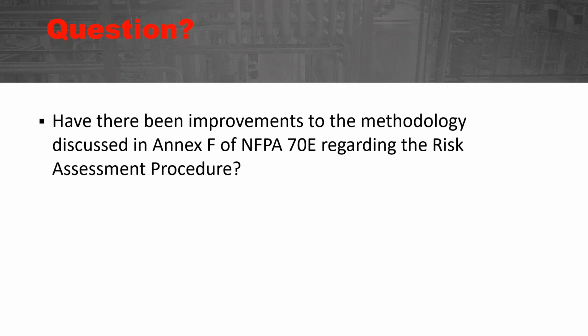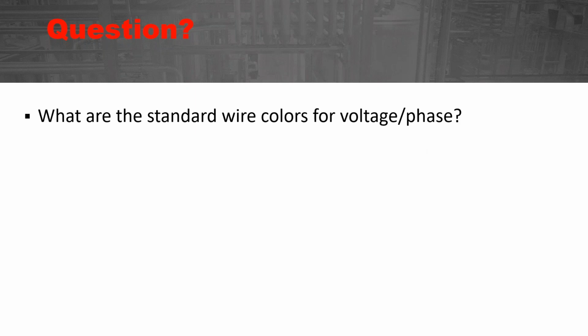Okay. Thanks, Charlie. So the next question is, what are the standard wire colors for voltage or phase? Is there a standard definition, Charlie? I think Bono put a lot of my questions right in a row here, which is fine. I'm used to talking. So what is the standard colors? A lot of times when I'm teaching either the National Electrical Code or 70E to electricians, maintenance people and engineers, I ask, what are the required colors for 120/208 volt three-phase? The general answer comes out: black, red, blue, and white for the neutral or the grounded conductor.